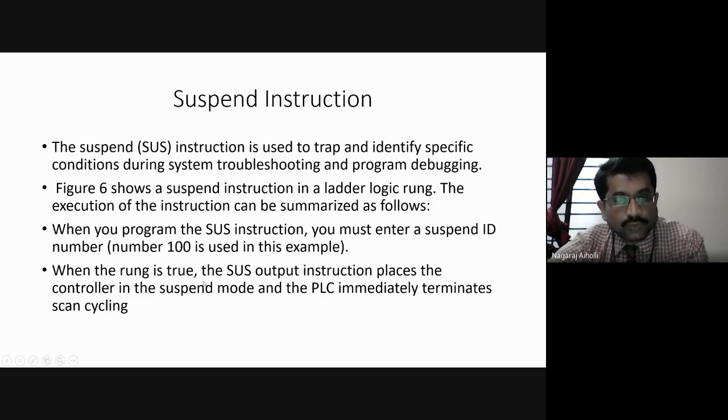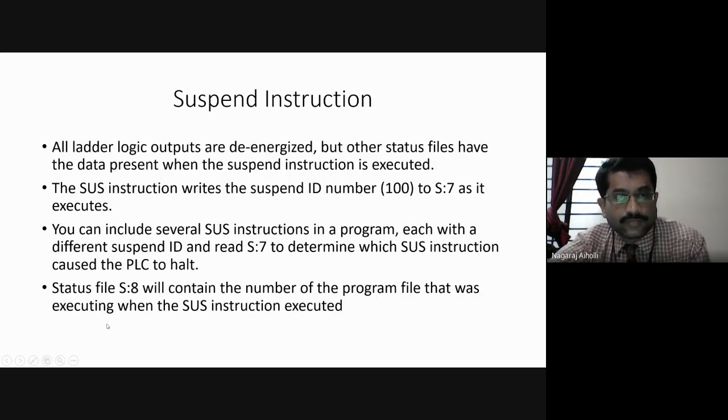When the rung is true, what will happen? The SUS output instruction places the controller in the suspend mode and the PLC immediately terminates the scanning process. Once the suspend instruction is executed, it will immediately stop the scanning process. All ladder logic outputs are de-energized, but the status files have the data present when the suspend instruction is executed. The status file data will remain as it is when this instruction is executed.